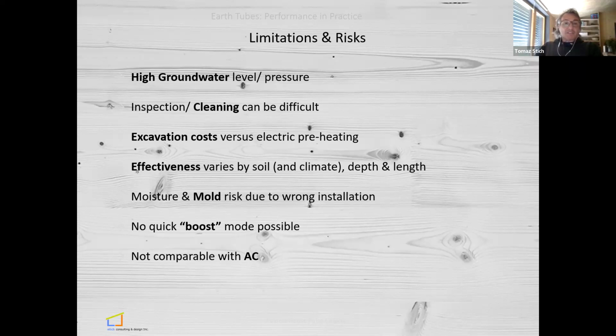Moisture and mold risk, this is the main disadvantage that always comes up with earth tubes. And I agree it can be a problem depending on the location. We are in Invermere, which is a very dry climate, so we don't have problems with moisture or mold at all. There's no quick boost mode possible. It always does what it does, and it's not comparable with an air conditioning unit. Okay.